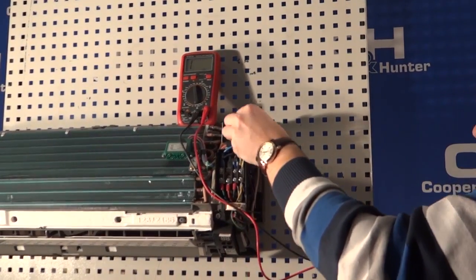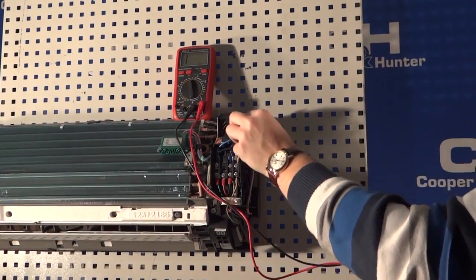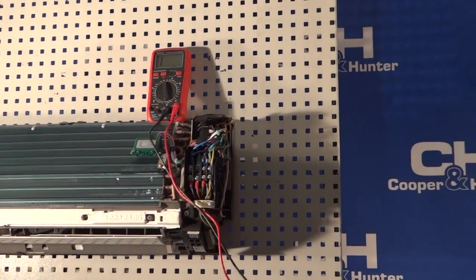If the sensors are in working order but still there is an error code, it is necessary to replace the main board of the indoor unit.